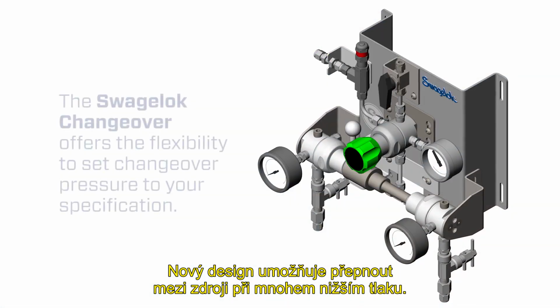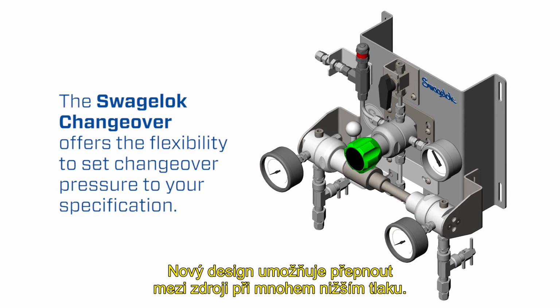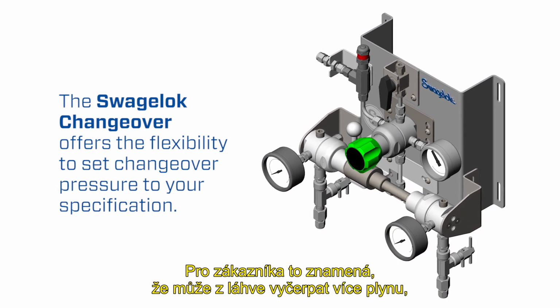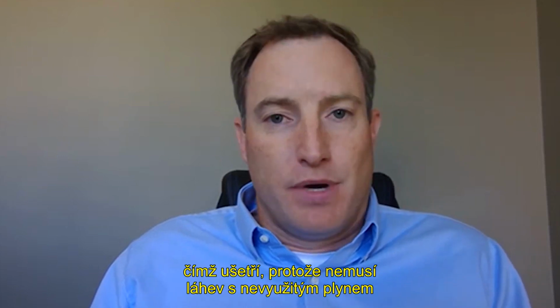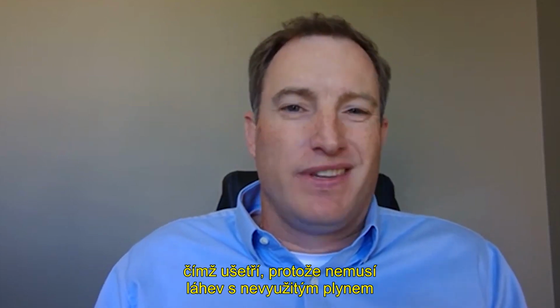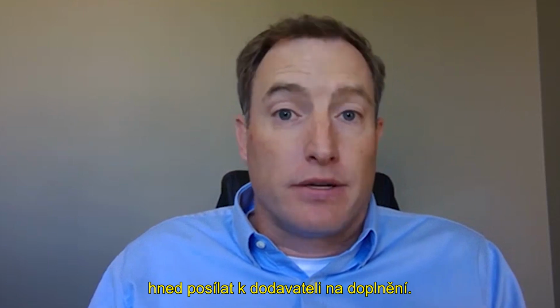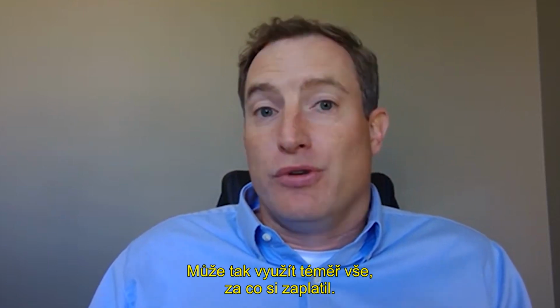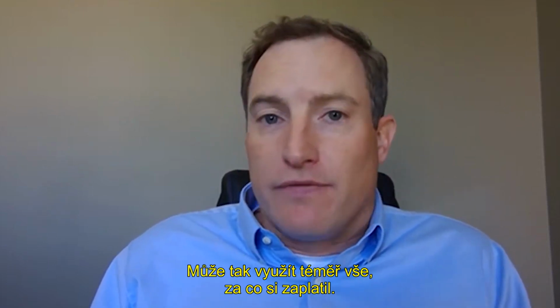The new design allows us to change over at a much lower pressure. So what does that do for our customers? It allows them to use more of the gas in the bottles, saving them money instead of replenishing the bottles and leaving excess gas in there and sending that back to the supplier. So now they're actually using everything or almost everything that they're paying for.